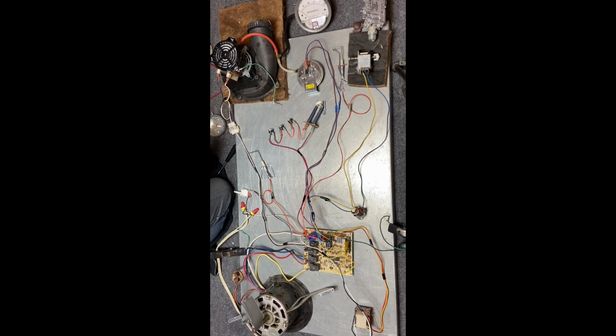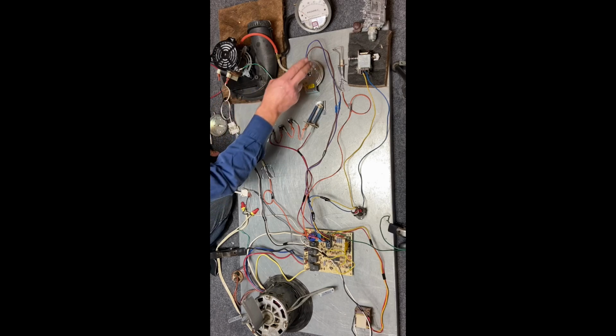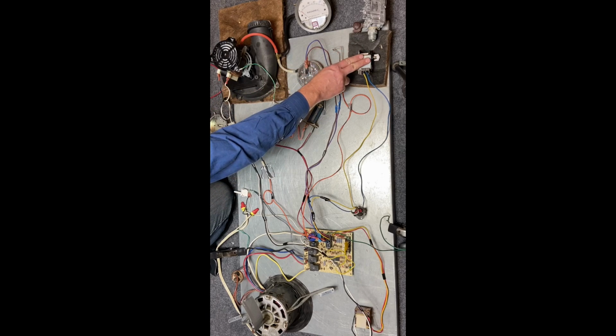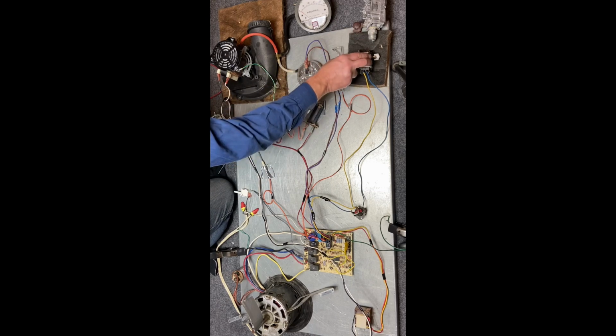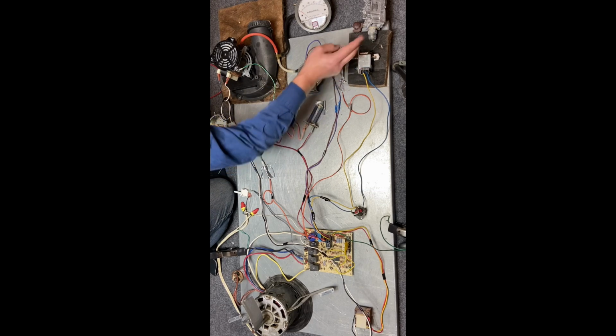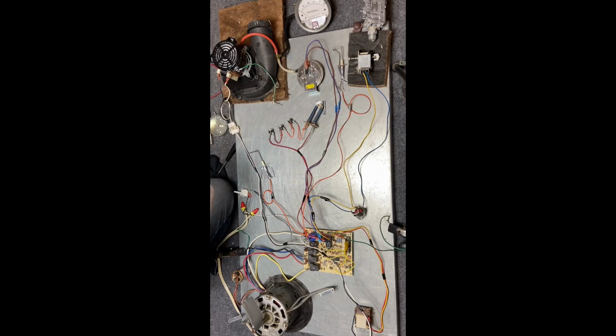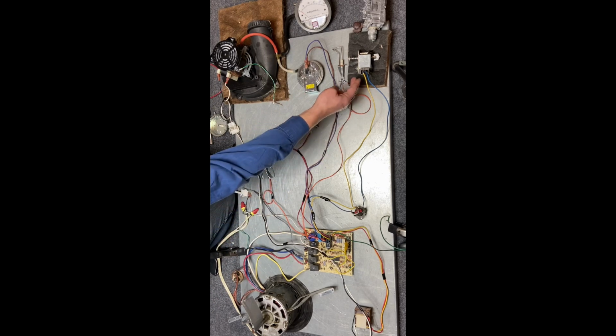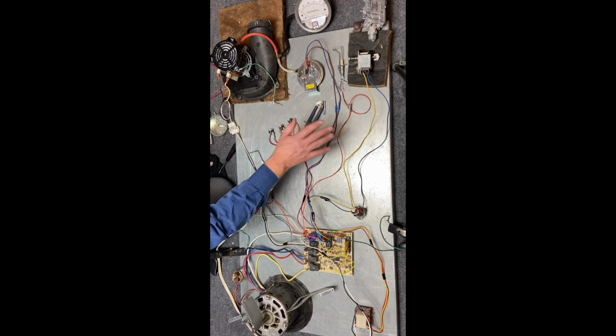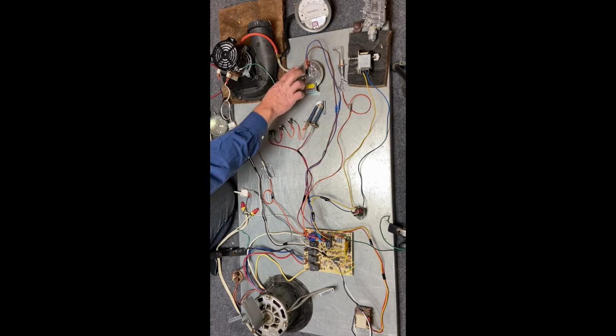I had an employee of mine that went to a customer's house and said they had a bad combination gas valve when in reality they didn't have gas to the house. So even though this solenoid switch was opening, there was no gas to flow through it. So now we've broken down these 2-wire components. Notice I didn't have 24 volts entirely, only in the correct sequence. So next we're going to check this pressure switch and see what's happening with our pressure switch.